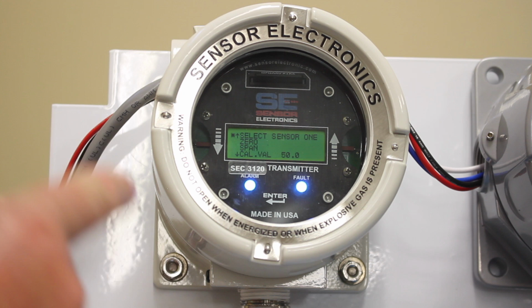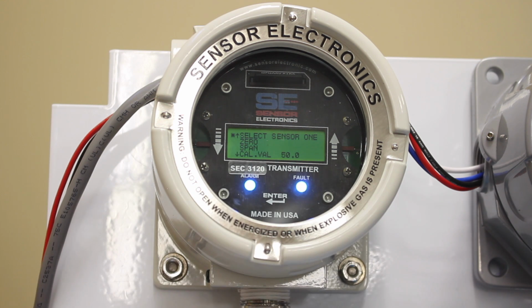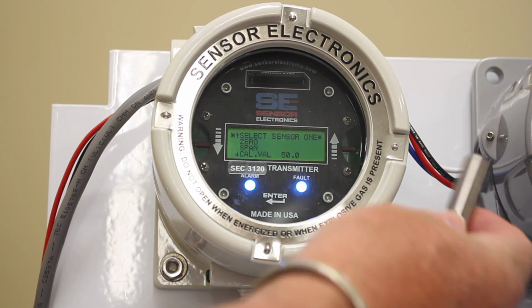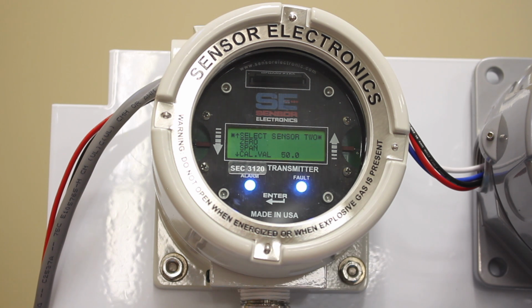mode. And since this has two sensors connected to it, you'll be able to select sensor number 1 or sensor number 2. So to select sensor number 1 or 2, you just go to enter, the cursor jumps over to the right side, and you can either select 2 or back to 1. And since the camera is on number 1, we'll calibrate number 1. So once the sensor is selected, to get rid of the cursor, you jump to the enter again.